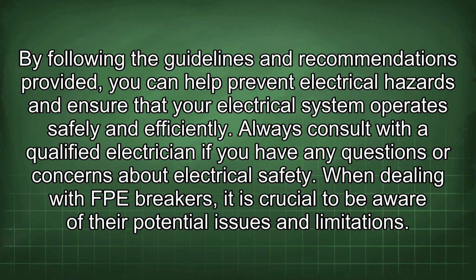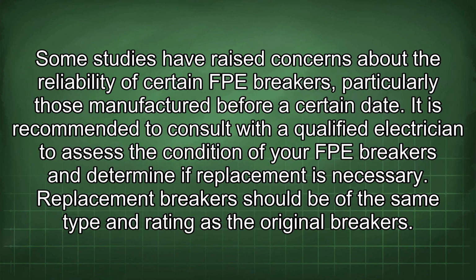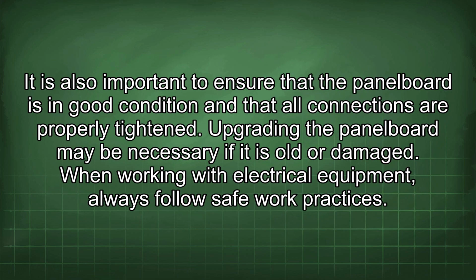When dealing with FPE breakers, it is crucial to be aware of their potential issues and limitations. Some studies have raised concerns about the reliability of certain FPE breakers, particularly those manufactured before a certain date. It is recommended to consult with a qualified electrician to assess the condition of your FPE breakers and determine if replacement is necessary. Replacement breakers should be of the same type and rating as the original breakers. It is also important to ensure that the panel board is in good condition and that all connections are properly tightened. Upgrading the panel board may be necessary if it is old or damaged.